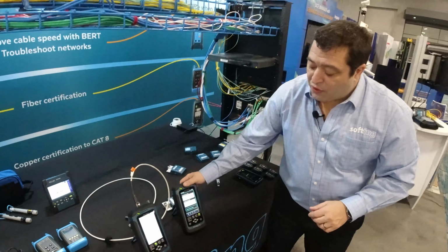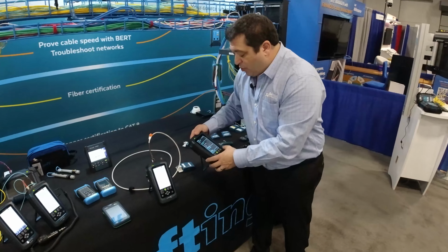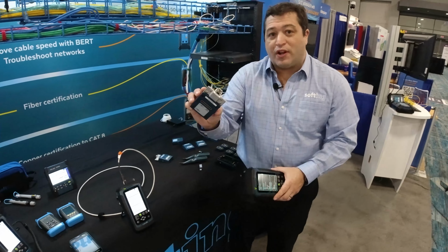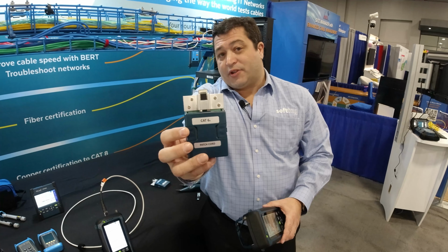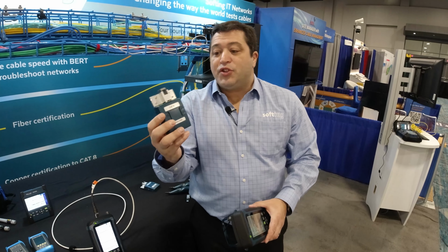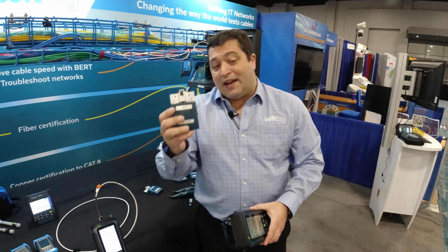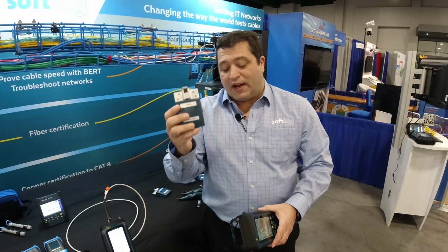That's giving you an RJ45 male to go into the patch panel. However, on the remote side, what you will have is a patch cord adapter. It is not a channel adapter. That is our patch cord adapter, okay? Now this gives you a different test plane and is key to making this measurement correctly, okay?